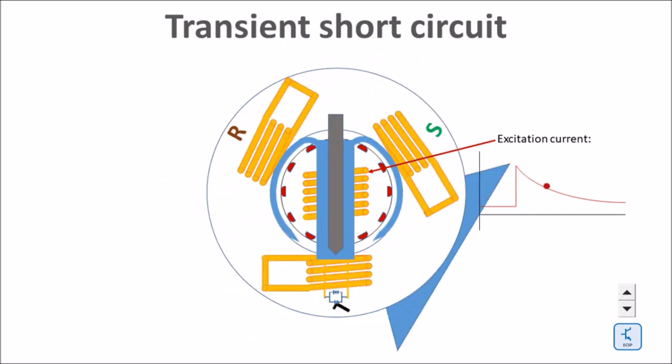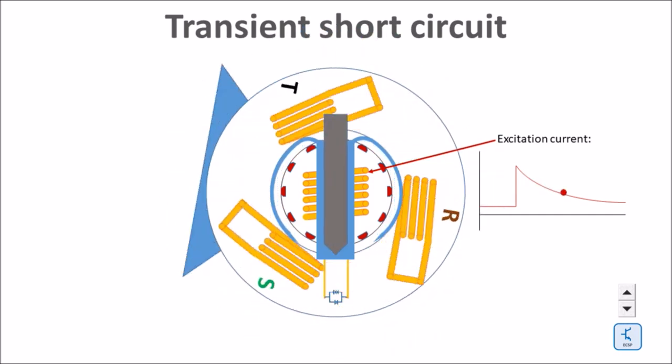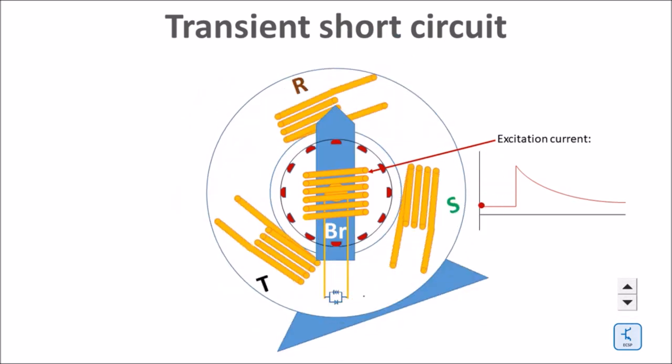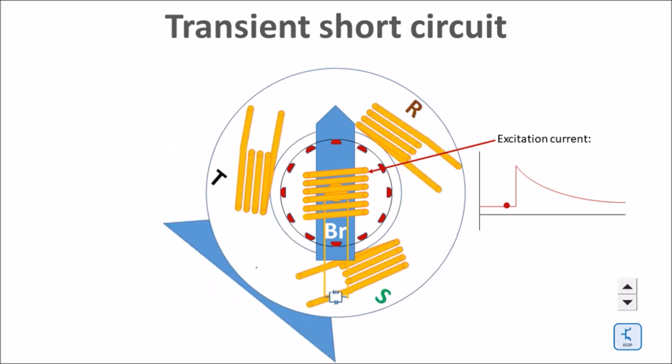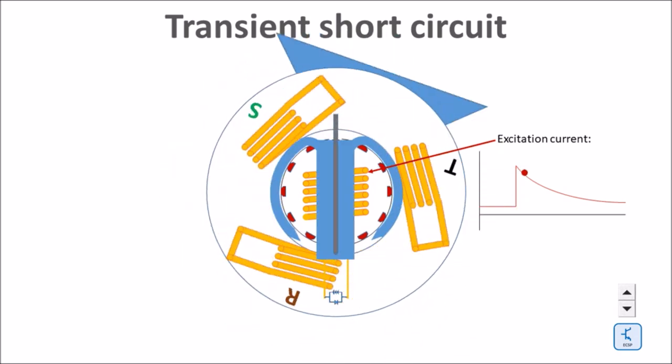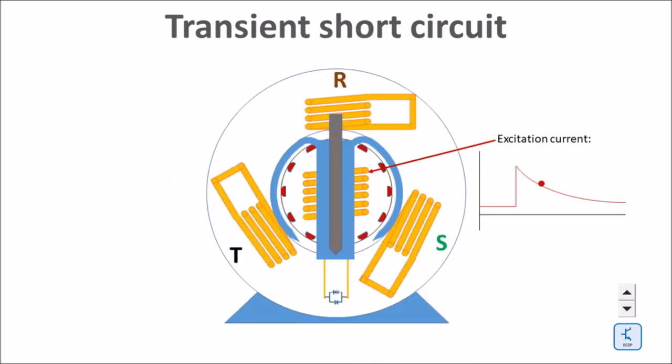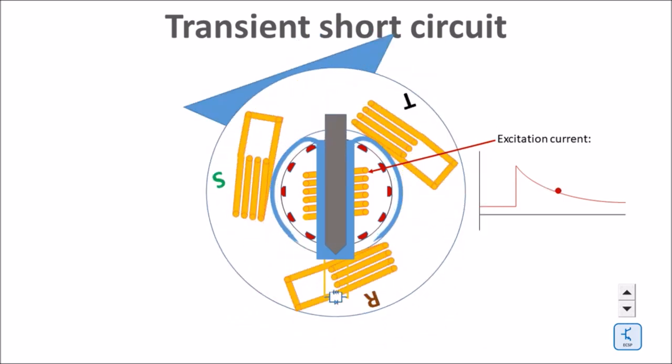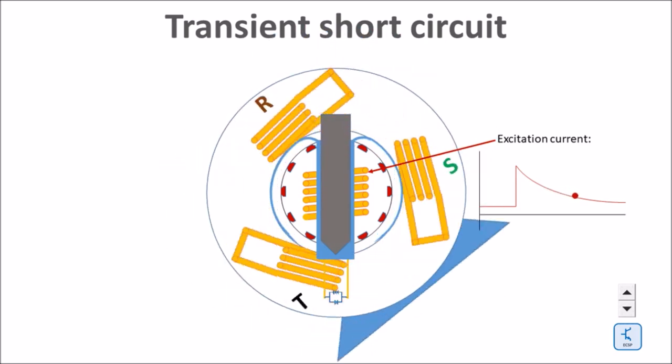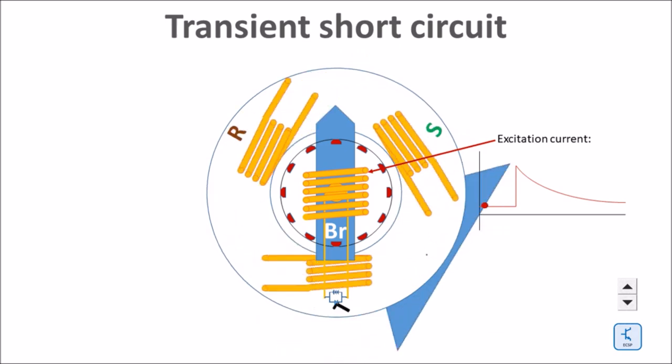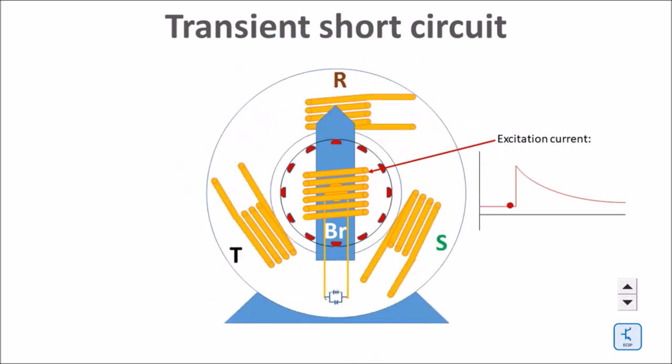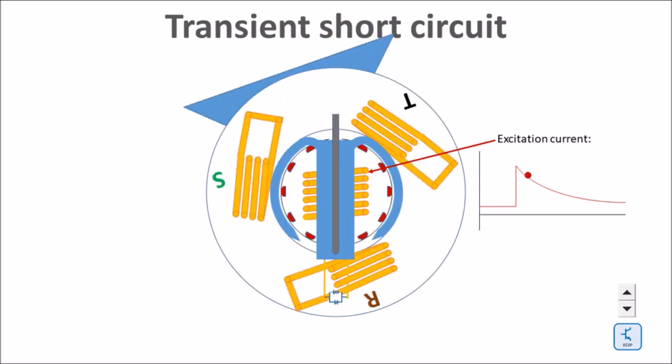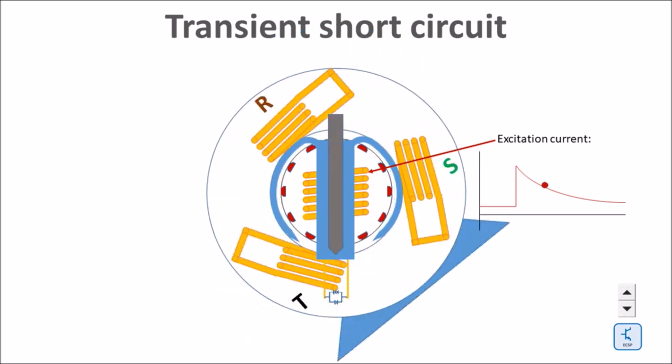The red curve to the right shows the excitation current jumping in order to block the field of the three phases to penetrate the rotor coil as well. Due to the inner resistance of the excitation coil, however, this block fades away and gradually the counter fields of the stator penetrate the rotor field. This translates into a gradually increasing impedance of the generator, which is equal to a smaller and smaller short circuit current.